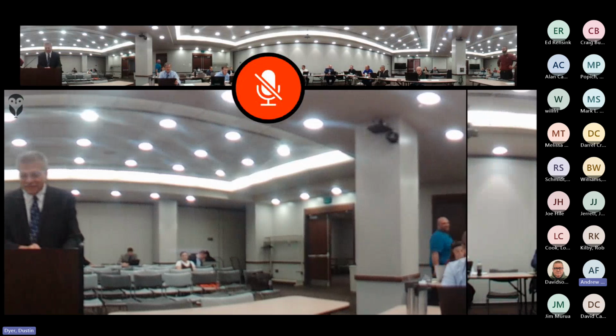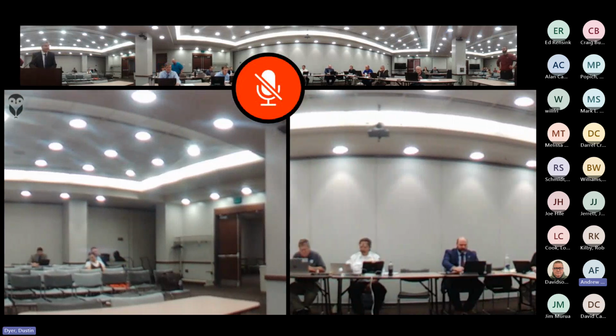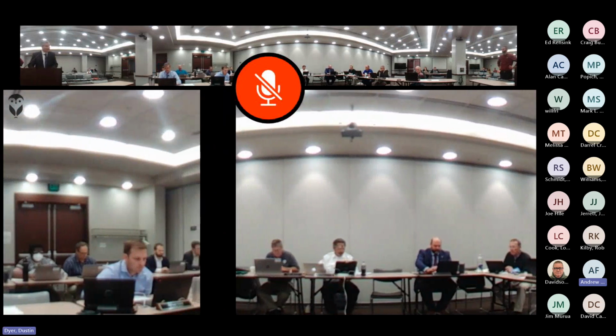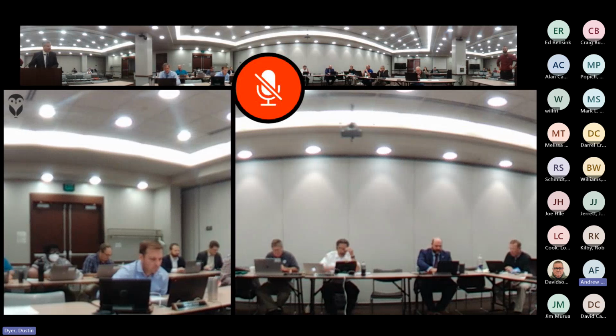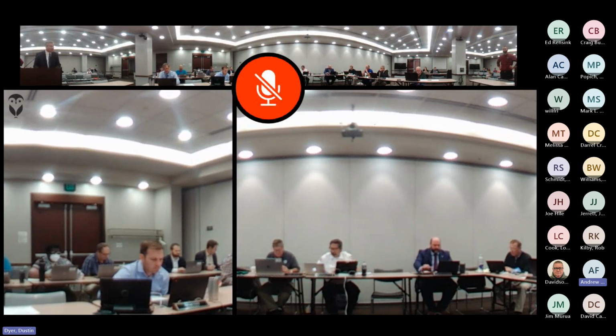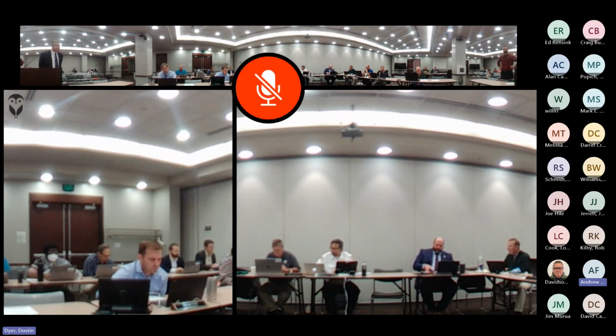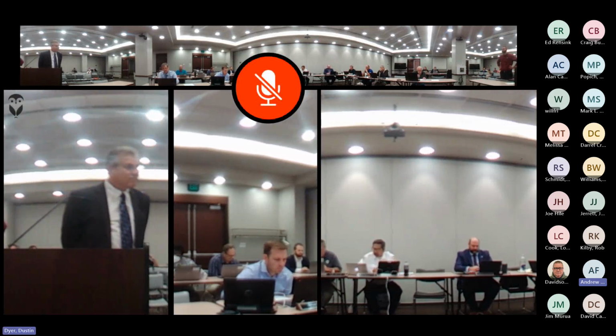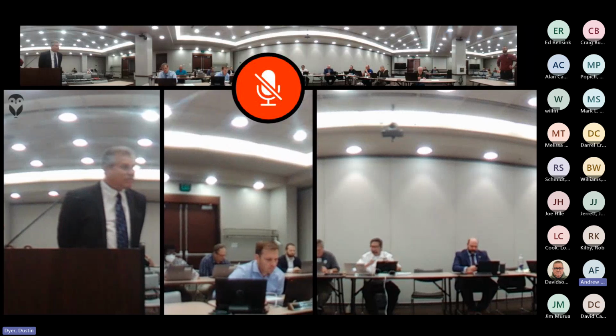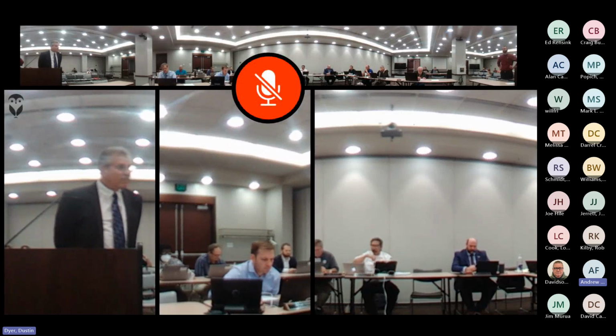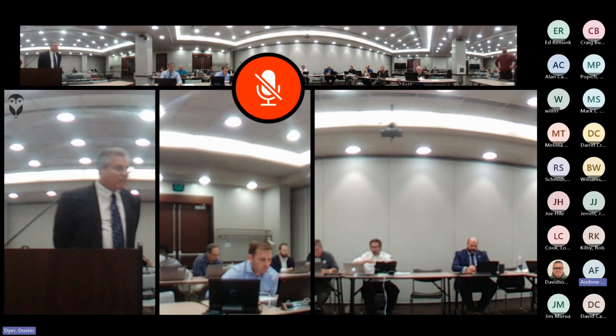So IDHS, please. Yeah, this is a new one we've come across and it's becoming more and more popular. They want to do a new type of refrigerant. It's an A2L group refrigerant. And they do not want to provide electrical wiring in regards to the Class 1 Division 2 wiring type.